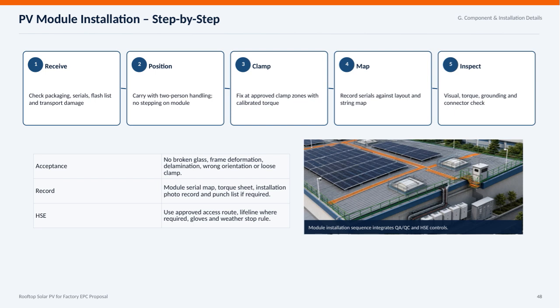The final step involves a thorough inspection, including visual checks, verifying torque settings, grounding, and connectors. Throughout the installation sequence, we integrate quality assurance and control measures alongside health, safety, and environmental protocols. This ensures no broken glass, frame deformation, delamination, wrong orientation, or loose clamps, while documenting all records meticulously and following approved safety procedures. This comprehensive approach guarantees a reliable and safe PV module installation every time.